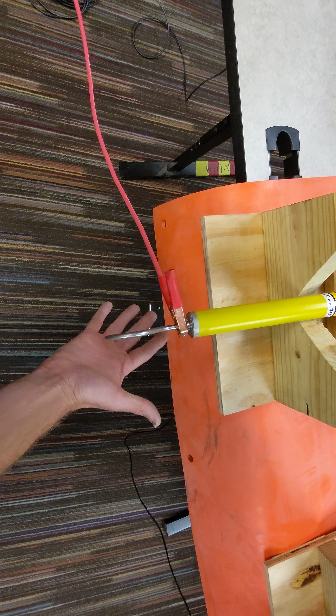This phasing meter that we're going to be using is actually a 6702 model. The model that has been quoted to the customer is calibration of a 6706 model. These are two very similar. The 6702, this model here, will measure from 0 to 40 kilovolts, and the 6706 model will measure from 0 to 20 kilovolts. That really truly being the only difference between the two. So, because of the fact that they're so close in similarities and even how they look, we're going to use this model to kind of use as a guinea pig.